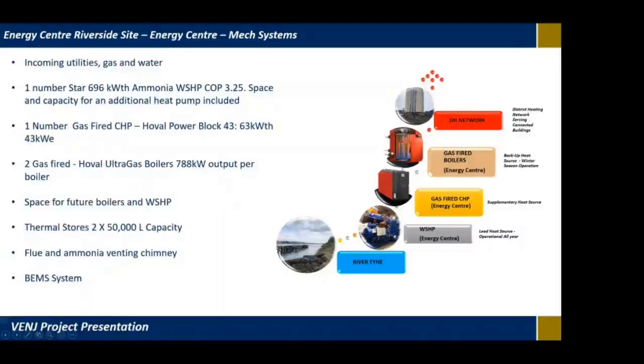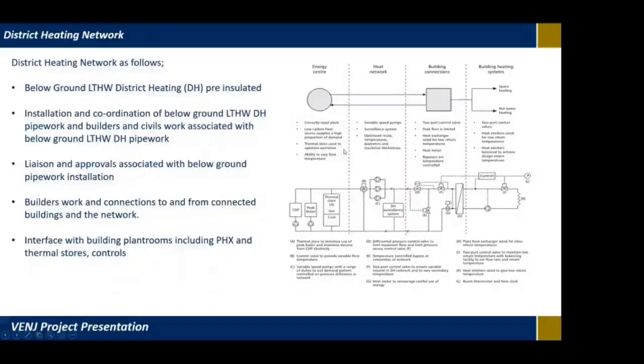The initial operation of the energy centre's pipework, in terms of flow and return temperatures, is 75-55 degrees C, but we're aiming to reduce that as the scheme develops. When the scheme's live, the council are potentially going to do some secondary side building modifications to try and lower that return temperature. But it's quite difficult to do that theoretically. A lot of that can be estimated theoretically, but you really need to have the scheme running and do some of your tweaks to try and optimize the network. So that's the aim, and that'll improve COPs, etc. as well.